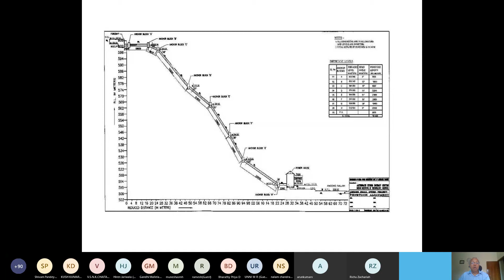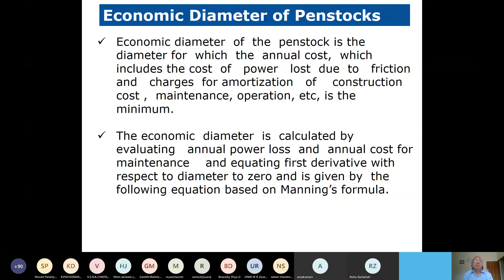An economic diameter penstock has to be chosen, because if I use a larger diameter, costs become high but losses are less. If I use a smaller diameter, the cost of the penstock is less but losses become high, and loss is nothing but money. So a lot of optimization happens on this—you have to take a balance, and this is called the economic diameter.